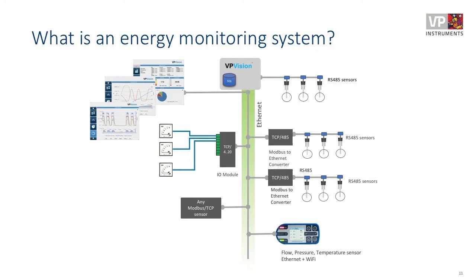Typically, in our case, VP Vision has a central logger, which we call the VP Vision M, which stores all the data. It's connected through Ethernet, which makes it quite easy to also do very large projects because it's standardized infrastructure. Then on that Ethernet connection, there could be analog sensors through a converter. There could be flow meters like the Flowscope M with a direct Ethernet output. Or there could be Modbus-based flow meters, also through a converter. And that's all nicely tied together on the network. The central VP Vision monitoring software stores all that data in a database and then visualizes it in different graphs. You can see KPIs, trends, alarms, etc.